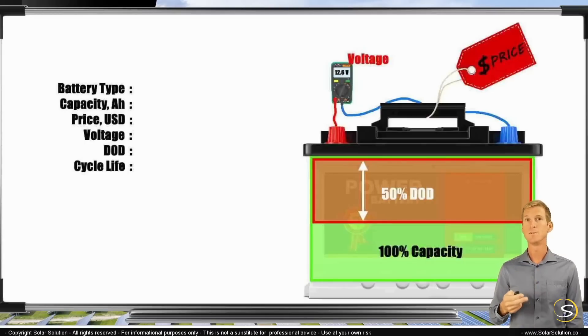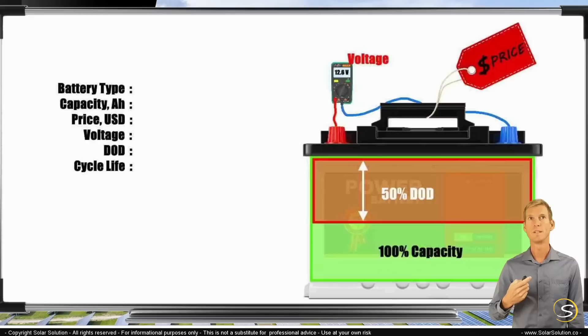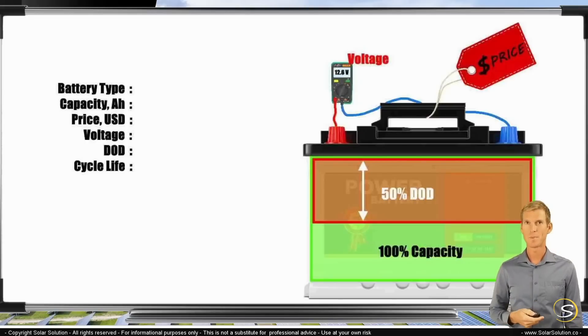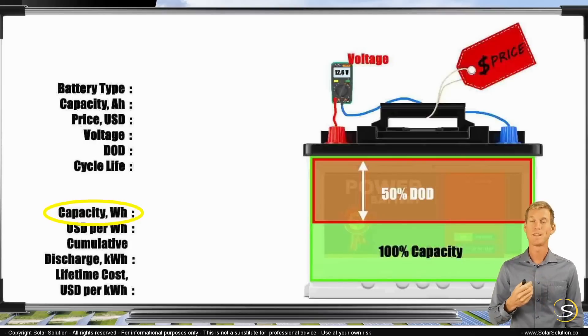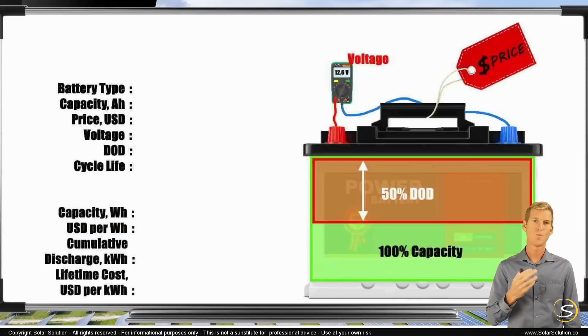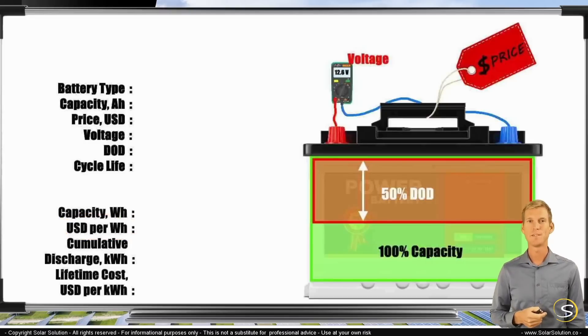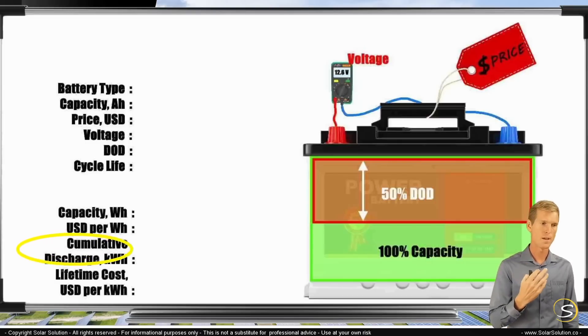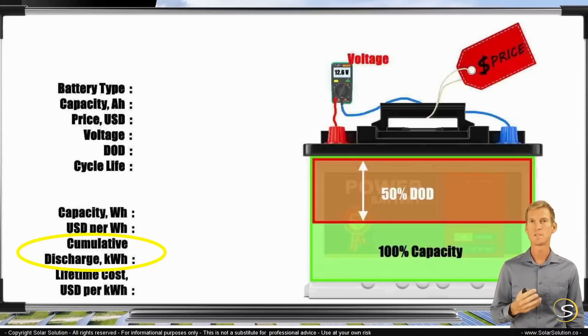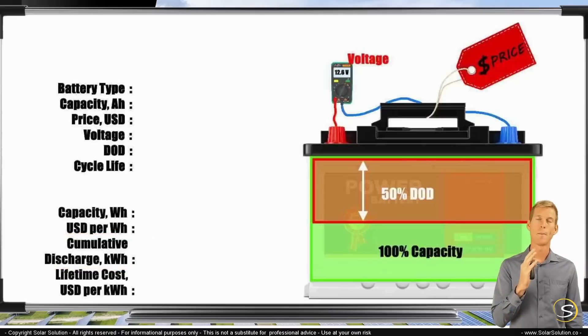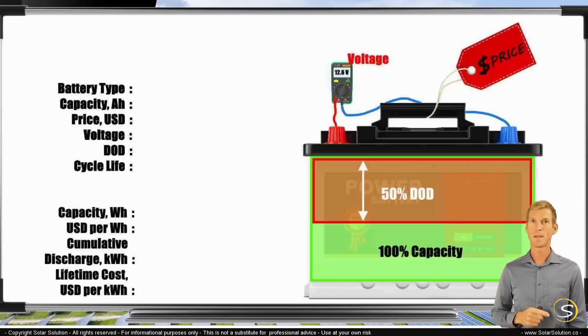Those values are relatively easy to get, but you need them to calculate the second set of values — the ones we actually use for the apples-to-apples comparison. First: capacity in watt hours. Second: dollar price per watt hour. Third: the cumulative amount of energy you can discharge over the battery's entire lifetime, normally expressed in kilowatt hours or megawatt hours. One megawatt hour equals 1,000 kilowatt hours; one kilowatt hour equals 1,000 watt hours.